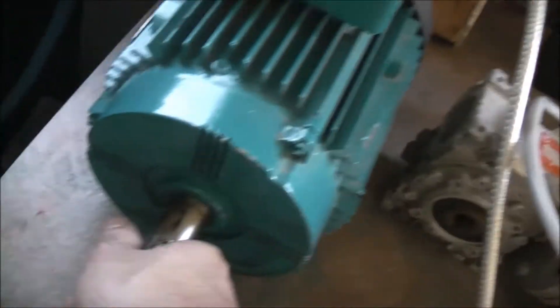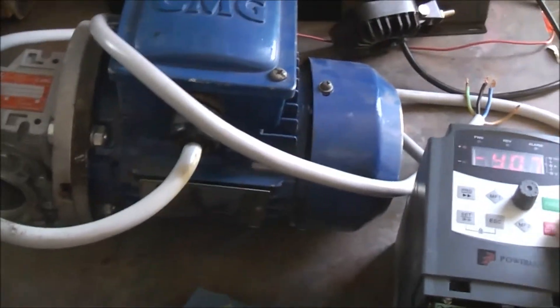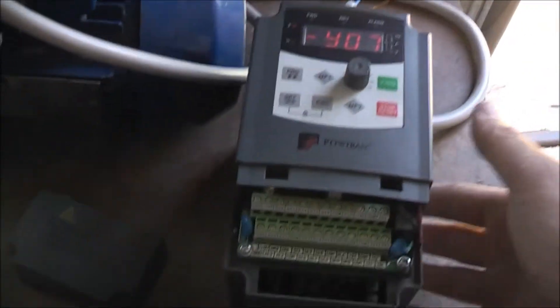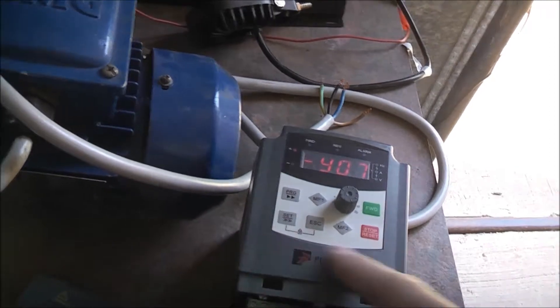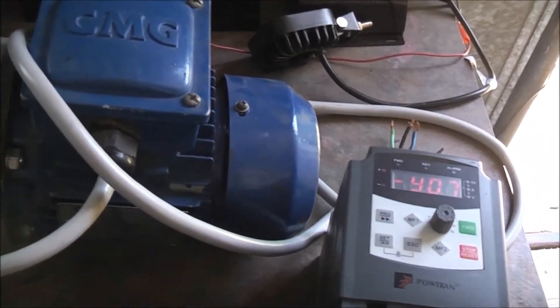It's not a current, voltage issue, or a phase dropout. It's strange, because it was working fine up until yesterday. I wanted to change the parameters for this motor because I wanted to test it. Now I was suddenly getting an EPG fault for some stupid reason.